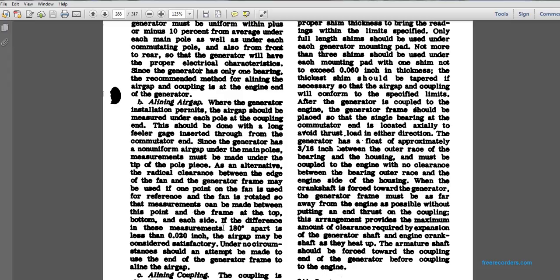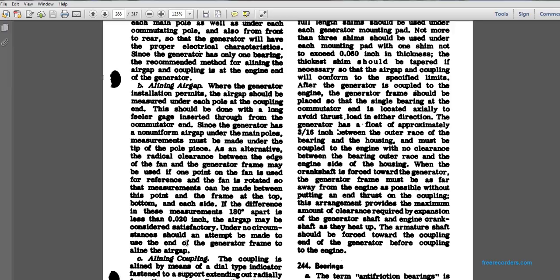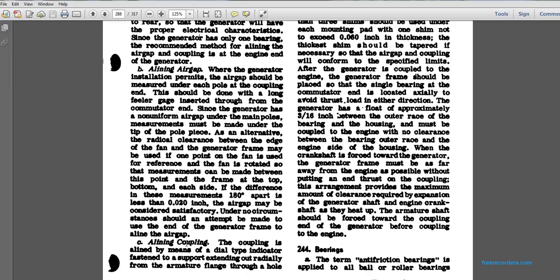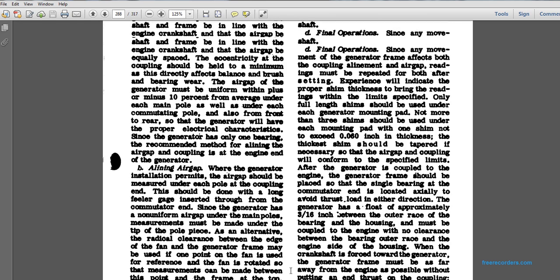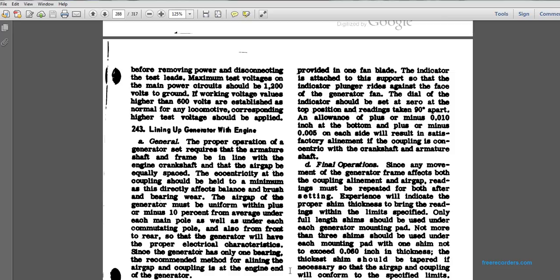If the difference measured at 180 degrees apart is less than 2/100 of an inch, the air gap may be considered satisfactory. Under no circumstances should an attempt be made to use this end of the generator frame to align an air gap. Lining up the coupling: the coupling is aligned by means of a dial type indicator fastened to a support extended out from the armature flange, through a hole provided in one fan blade.